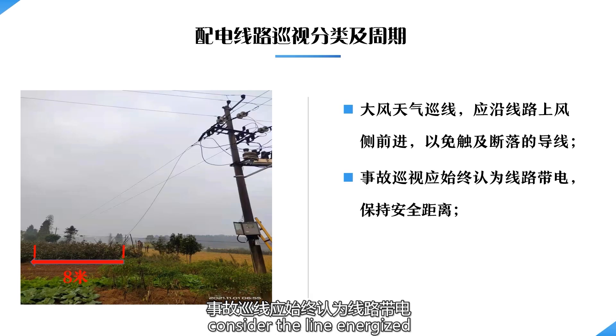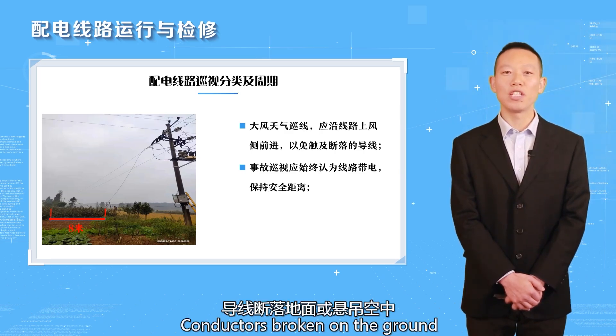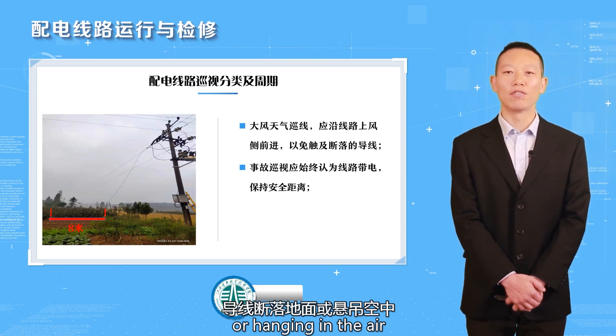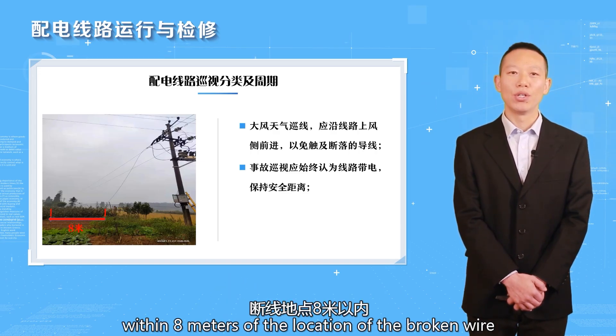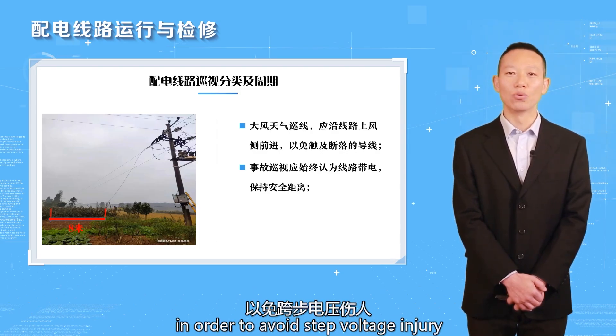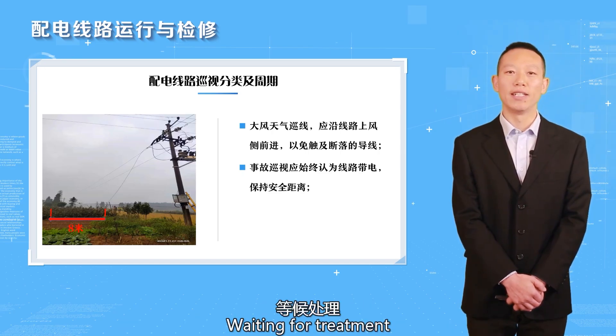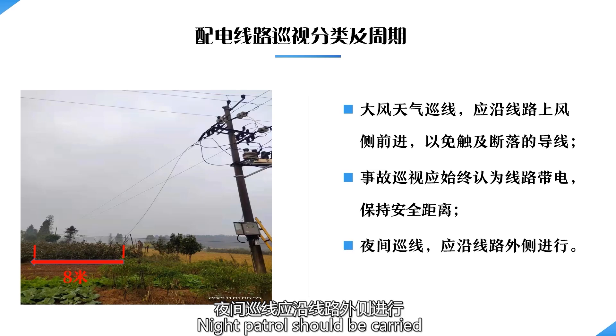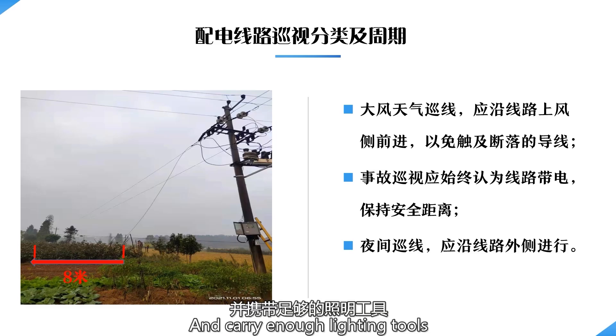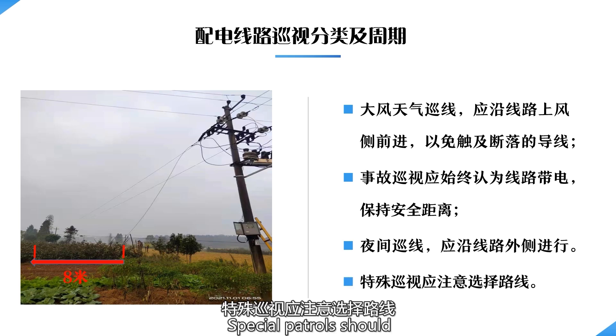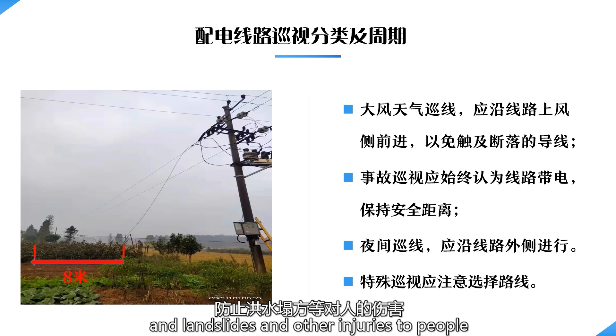Accident patrol should always consider the line as energized and maintain a safe distance. If the inspector finds conductors broken on the ground or hanging in the air, try to prevent pedestrians from approaching within eight meters of the location of the broken wire to avoid step voltage injury, and quickly report to the dispatcher and superior while waiting for treatment. Night patrol should be carried out along the outside of the line with sufficient lighting tools. Special patrol should pay attention to route selection to prevent flooding, landslide, and other injuries to people.